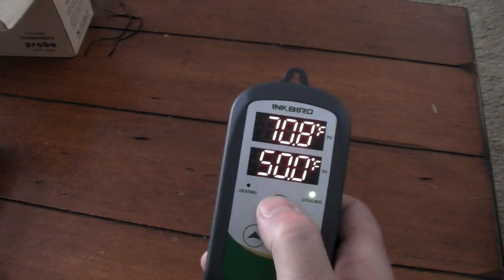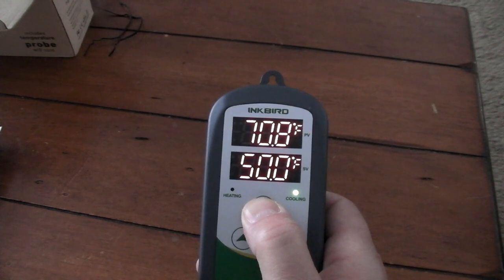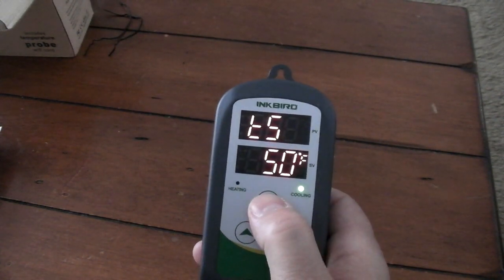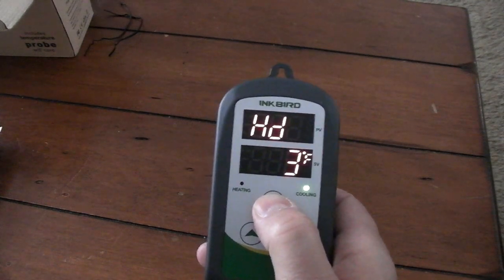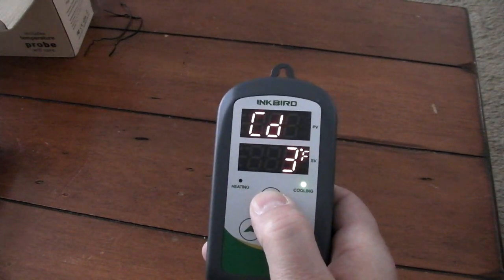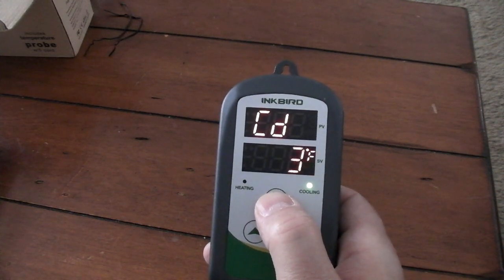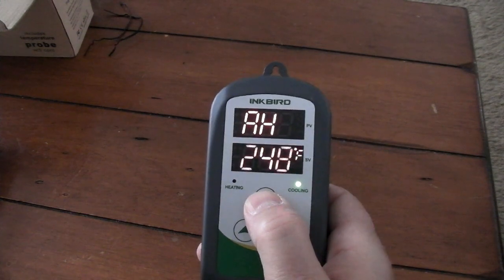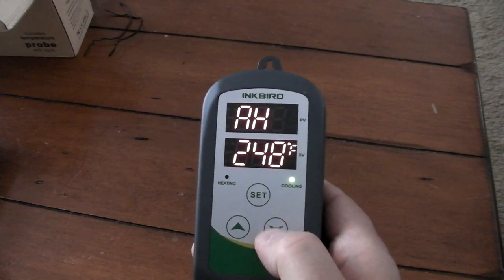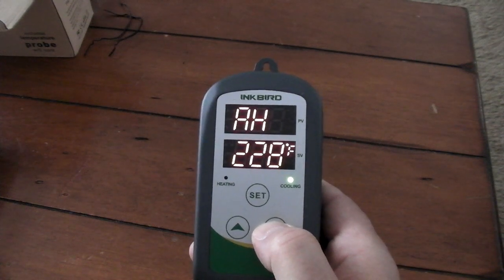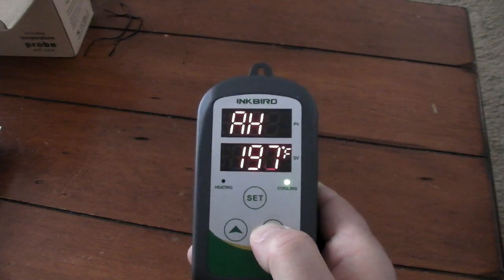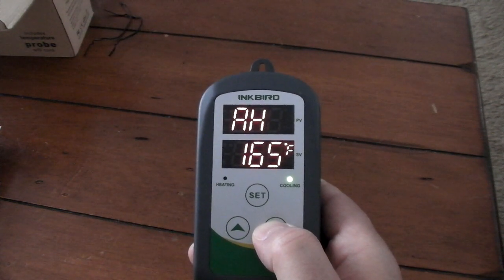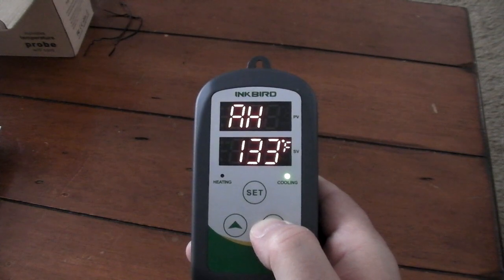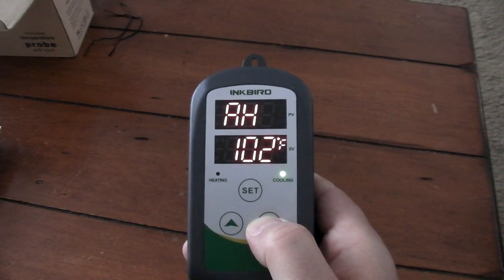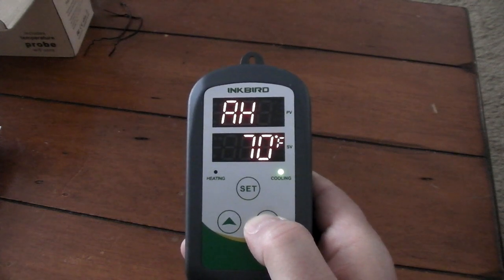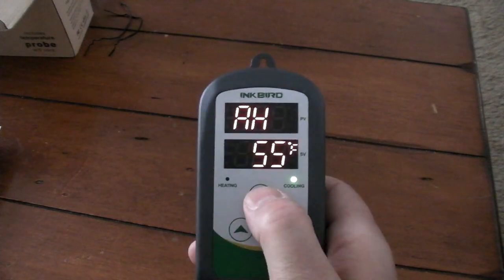And then some other features I'll go through here. Let's press and hold that. And so that's your temperature set. HD is heating differential. CD, cooling differential, 3 degrees, so you can change that. Alarm high limit. We're going to turn that down. Since I have my temperature set to 50, we're going to have it alarm at like 60 degrees. Or 55, let's change it to 55 degrees. So it'll alarm if it gets too warm. Hold set on that.